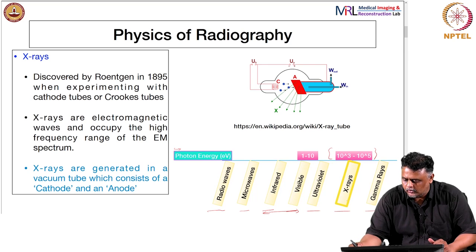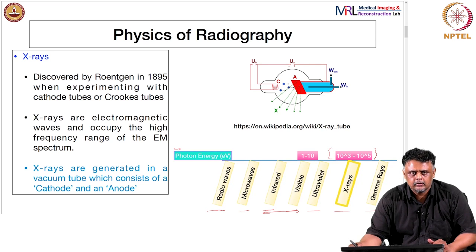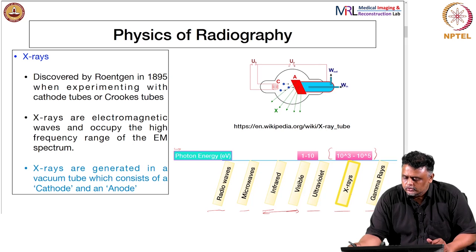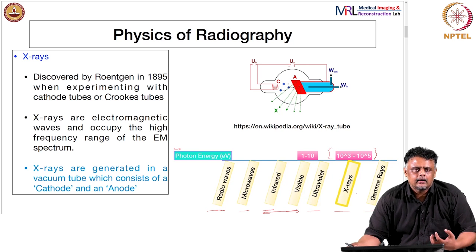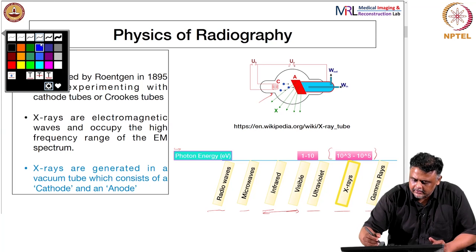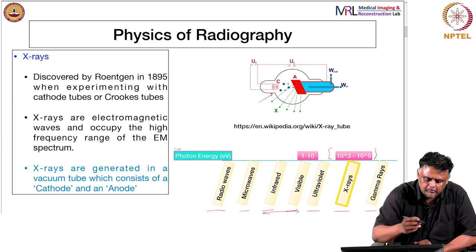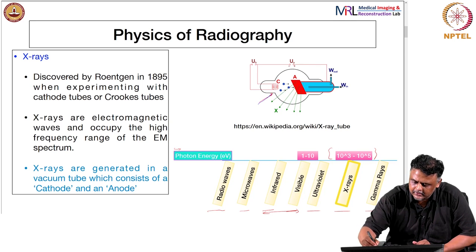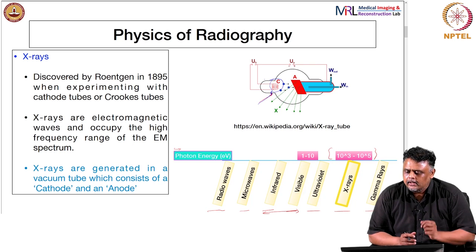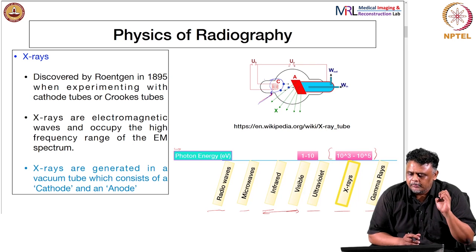Because x-rays are slightly high energy, they can cause damage at the cellular level. There are many safety procedures in place to avoid overexposure when examining a patient. In a modern x-ray tube, which is part of an x-ray radiograph imaging system, a vacuum tube consists of a cathode — essentially a filament of wire. That cathode is the emitter of electrons via thermionic emission: pass current through it, it heats up and emits electrons.